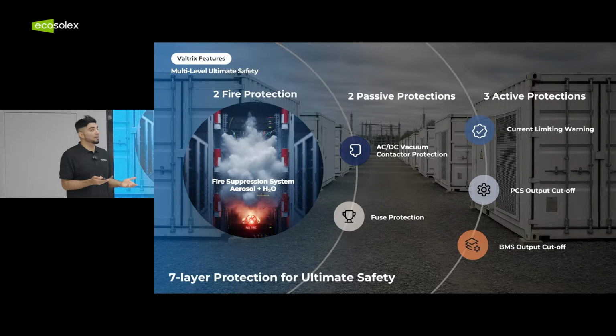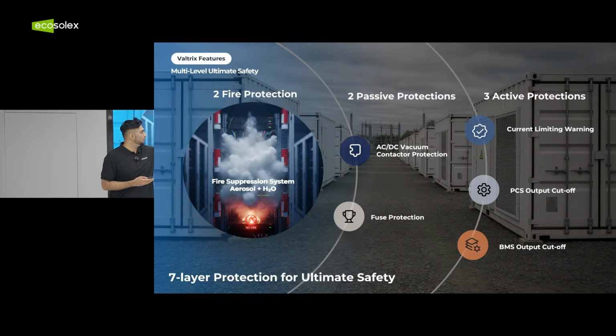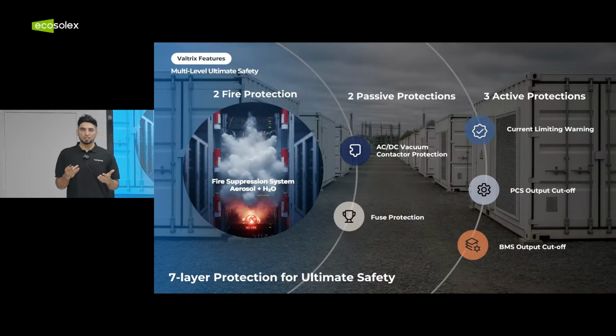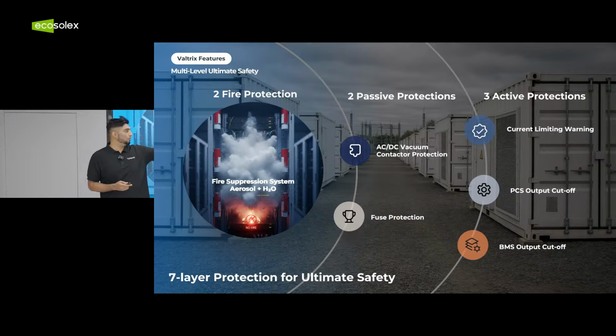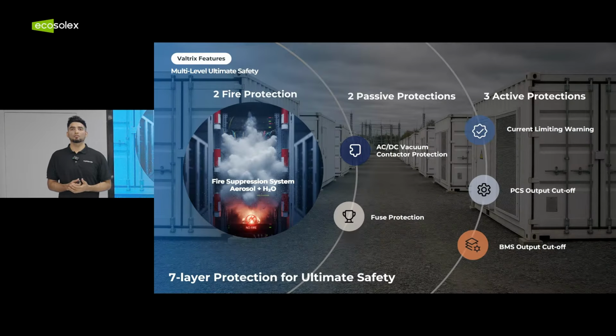Our safety philosophy is built on a 7-layer protection system for ultimate safety. This includes 2 fire protection, 2 passive protection, and 3 active protection. Mechanically, we use AC/DC vacuum contactor protection and fuse protection. Logically, we have strict cutoff protocol, current limiting warning, PCS output cutoff, and BMS output cutoff. Our goal is simple: no fire.